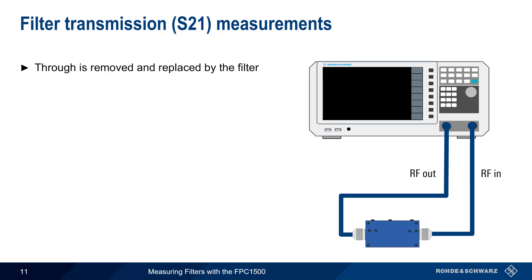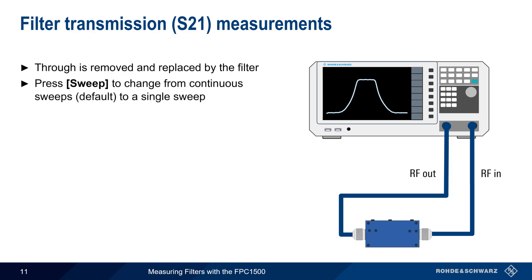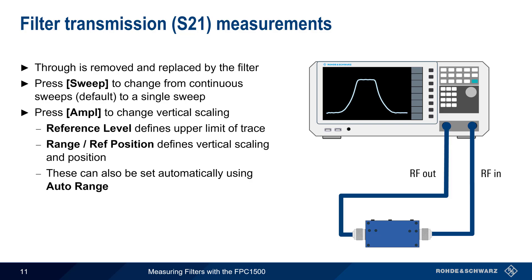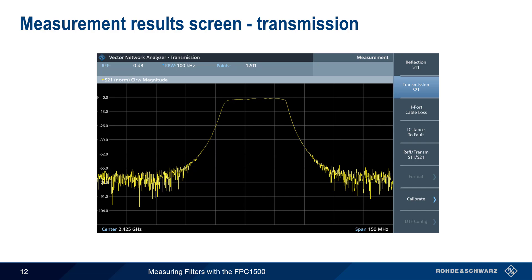By default, the FPC will sweep and update measurement results continuously, but this can be changed to a single sweep by pressing the Sweep hard key. The vertical scaling can be adjusted using the Amplitude hard key. The reference level is used to define the upper limit of a trace, and Range Reference Position is used to scale the trace vertically and to move the trace up or down. Note that the FPC also has an Auto Range key that can adjust these values automatically. Here is an example of a bandpass filter measurement.